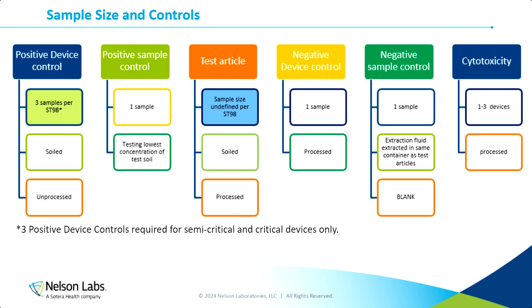We then move into our test articles. There's not a sample size defined in ST98, and I'll go into that a little further, but previously 3 was the known sample size. There have been some discussions about moving to 6 and 9 for semi-critical and critical devices. These test articles are the devices that get soiled and taken through the cleaning process, and then we perform the extraction and test for those endpoints. The next is the negative device control. The negative device control is just one sample that goes through the cleaning process.